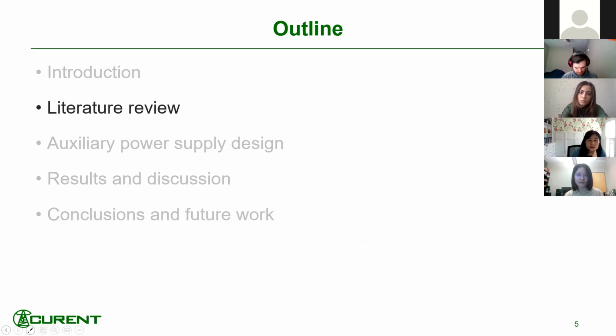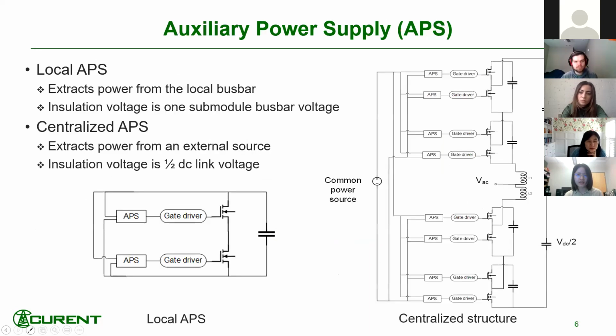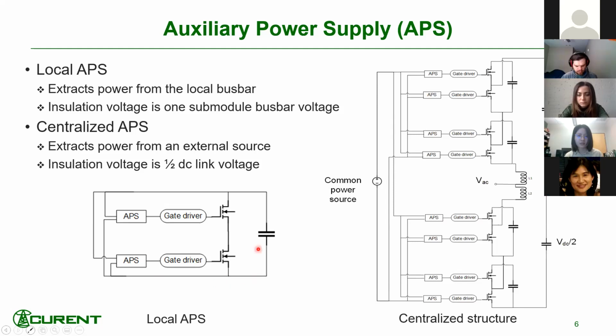Next comes the literature review. Typically the auxiliary power supply is divided into two types. One is the local APS. Here you can see this local APS extracts power from the local bus bar. And so the insulation voltage required for this kind of APS is that of one submodule bus bar voltage.